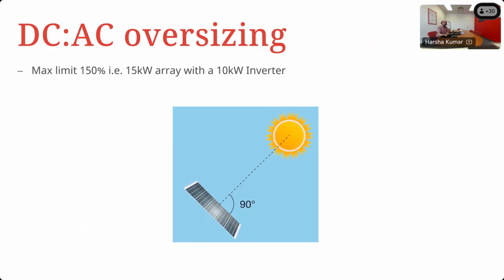Okay. And also we know that when you do oversize it, there will be seasons of the year when you will tend to clip because it is oversized. But the flip side of that is during conditions of low light or cloudy weather, you could still potentially get the inverter working at capacity simply because you've oversized the PV array by that much.